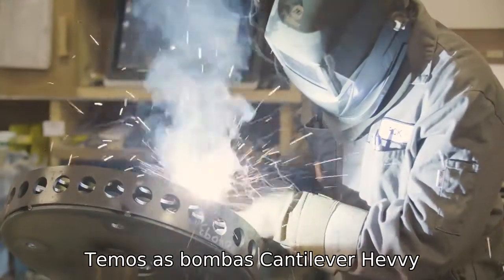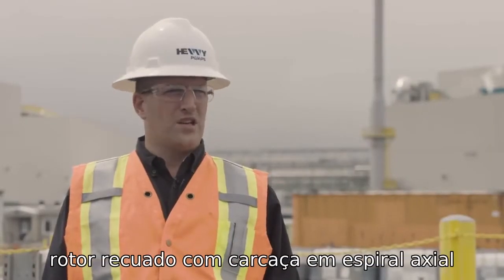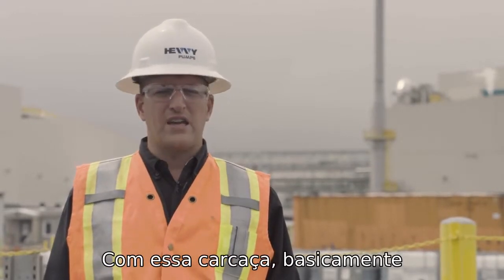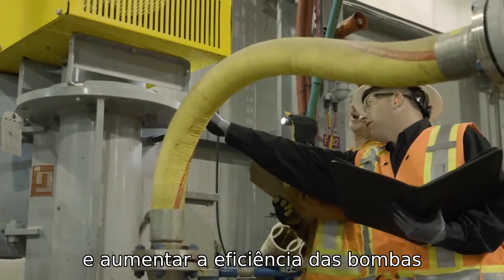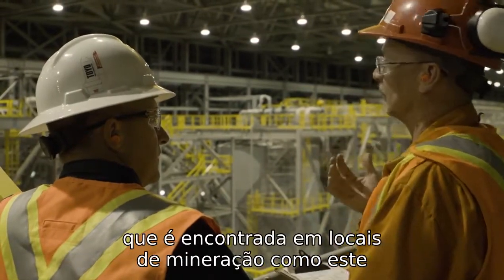We have the Hevvy cantilever pumps. Most of the pumps we have out are all with our vortex impeller and our unique axial spiral casing. With that casing, we have been able to reduce the wear rate through the pumps and increase the efficiencies so they can better handle the abrasive slurries that you find on mine sites like this.